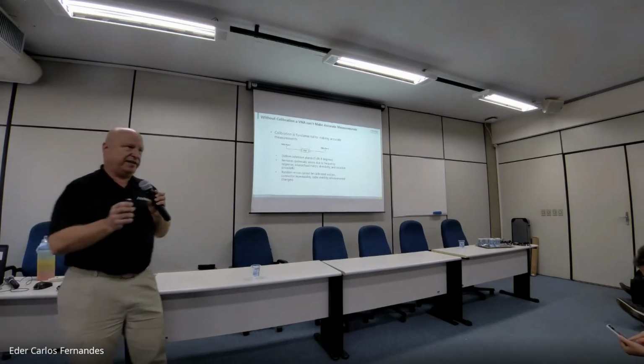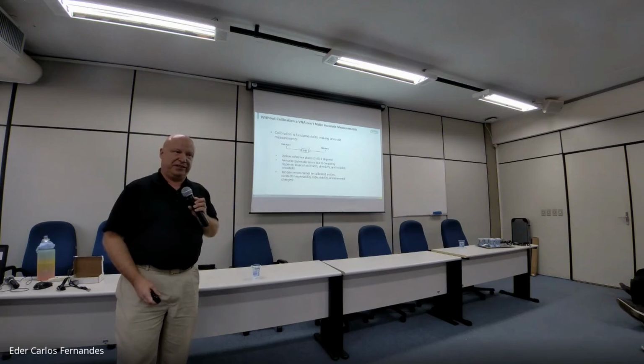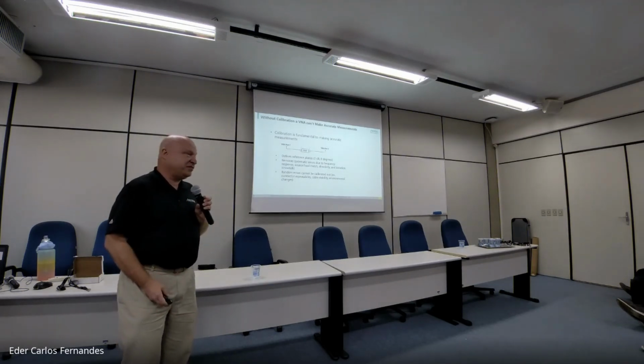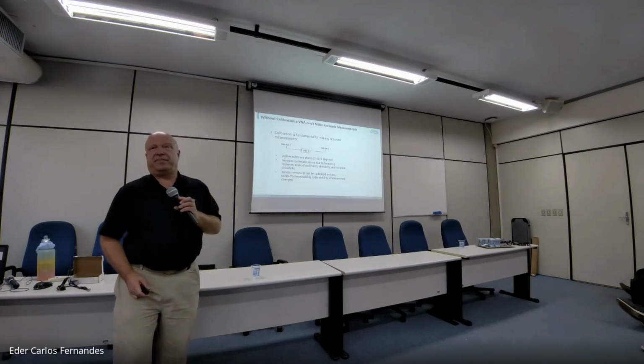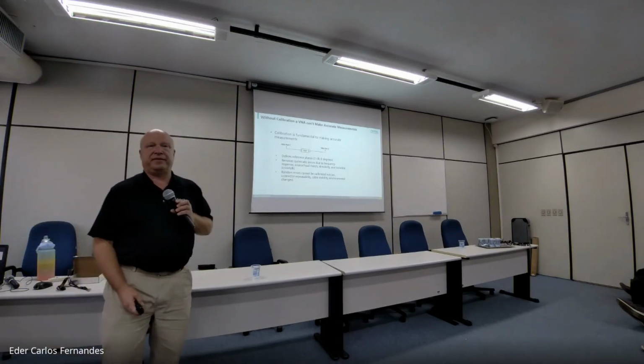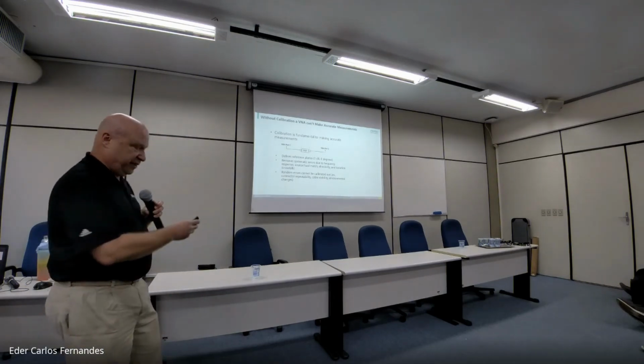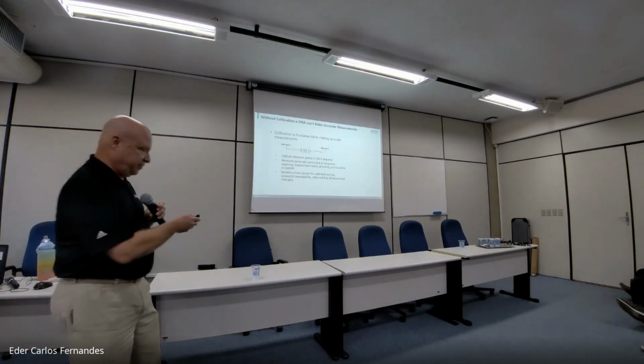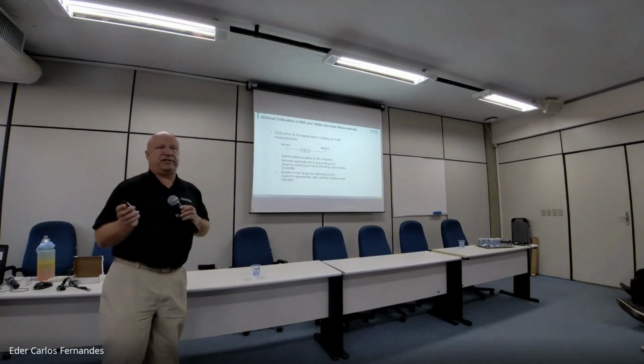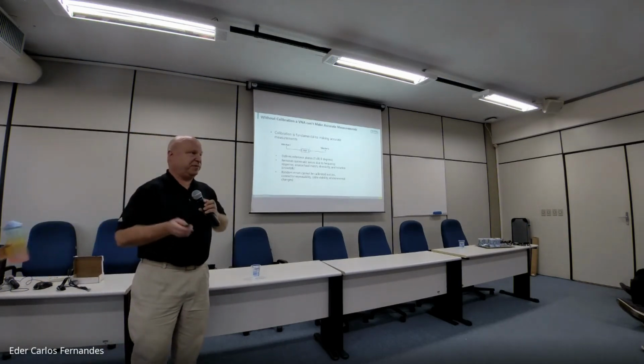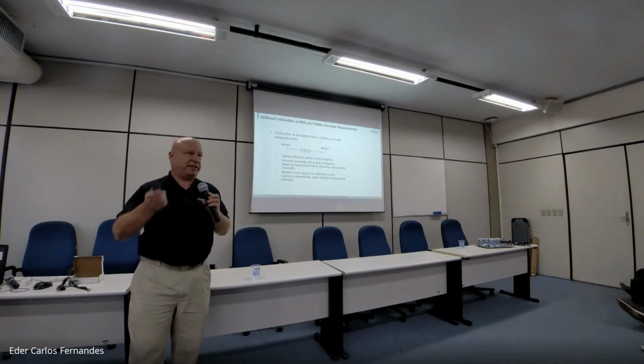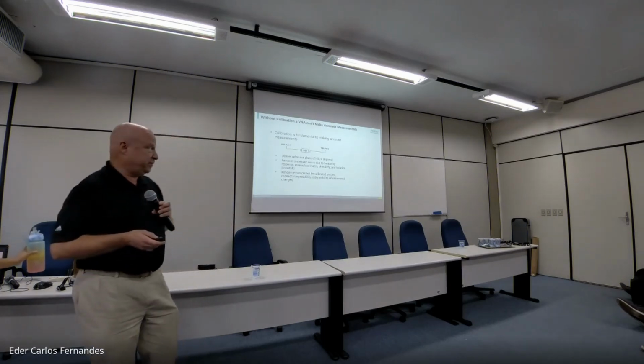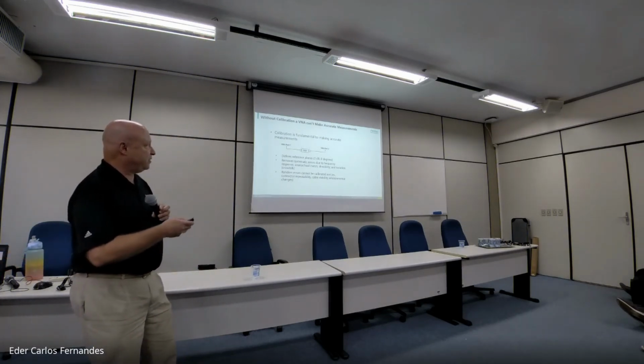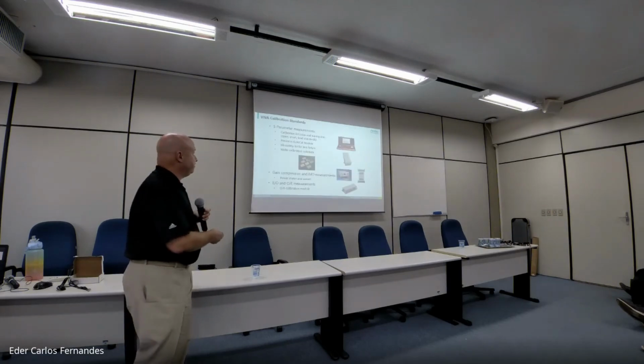Nine out of 10 times when somebody calls me and tells me their measurement is no good, my first question is, what cables are you using? I'm not even concerned so much with the instrument nor the device they're testing, but the cables tend to be the problem 9 out of 10 times. That's causing drift or causing something that's intermittent. And then environmental changes. Yeah, we can control the temperature of the room as much as possible, but there will still be some changes. Obviously, you want to keep the instrument on long enough so that things stabilize, but they're going to drift over time and temperature. And so those are things that we just try to control, but you can't completely eliminate.